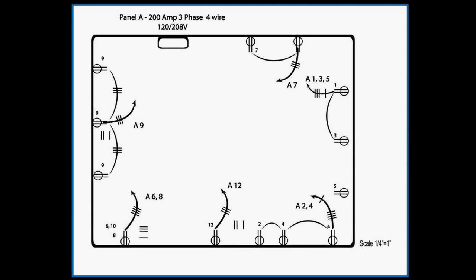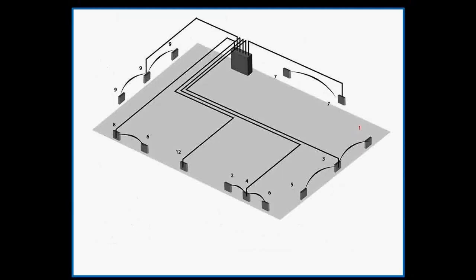To better understand what the two-dimensional drawing represents, I'll also use a three-dimensional drawing of the same building. This shows how the conduit runs out of the top of the panels to the junction boxes. From the junction boxes, the circuits extend an MC cable to the devices. Blueprints do not give three-dimensional detail, but oftentimes when a drawing shows a home run, it shows it with a curly Q arrow illustrating which circuits are running home or to the panel.